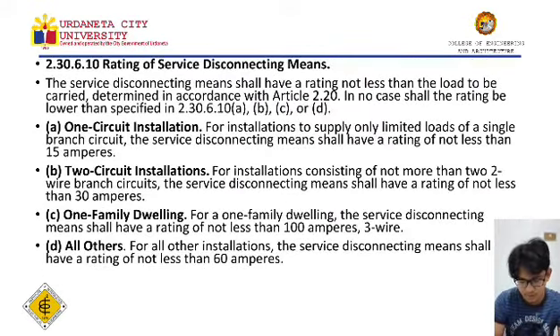Rating of service disconnecting means. The service disconnecting means shall have a rating not less than the load to be carried determined in accordance with Article 2.20. In no case shall the rating be lower than specified in 2.30.6.10. So, yung way po ng pag-disconnect ng service ay dapat may ratings na hindi bababa sa load na dadalhin na tinutukoy sa Article 2.20. Hindi dapat mas mababa ang rating kaysa sa 1 circuit installation, 2 circuit installation, 1 family dwelling, at lahat ng iba pa.